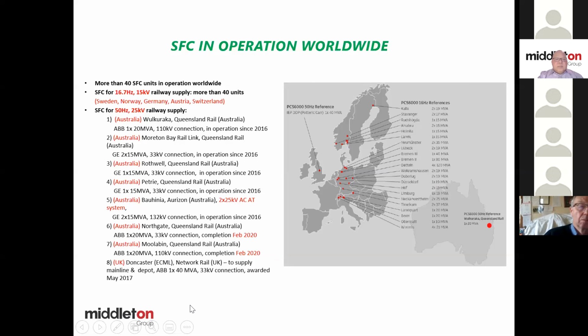In the UK, 1 unit has been installed, might be 2 units, on the East Coast main line near Doncaster. So the original idea was to bring in 132 kV supply to feed the conventional feeder station. And in the end, someone realized that it may be cheaper to use static frequency converter, SFC. So they actually installed 2 units and 40 MVA. So it's got to be 2 times 20 MVA. One feeds the new depot in the area, and one feeds the main line. And that lifted the voltage to allow the new Hitachi train to run happily across that section. So you can see it's dotted everywhere, and there are lots of them in Germany.